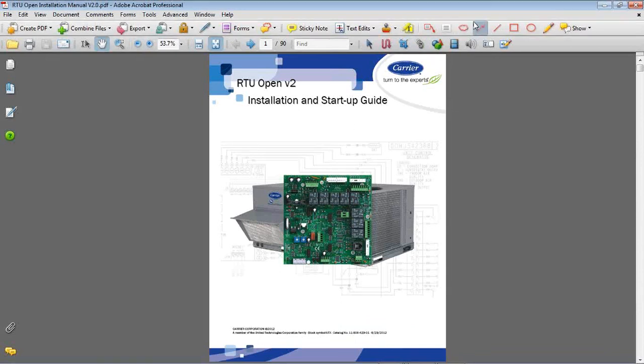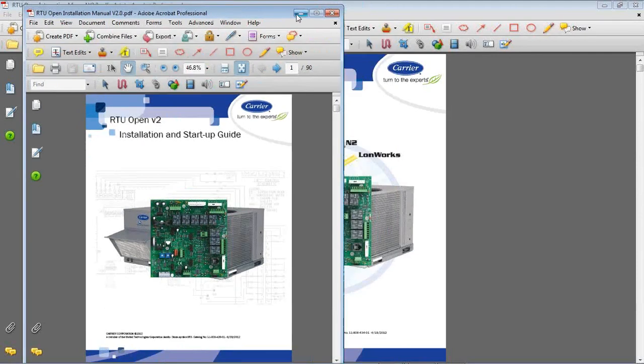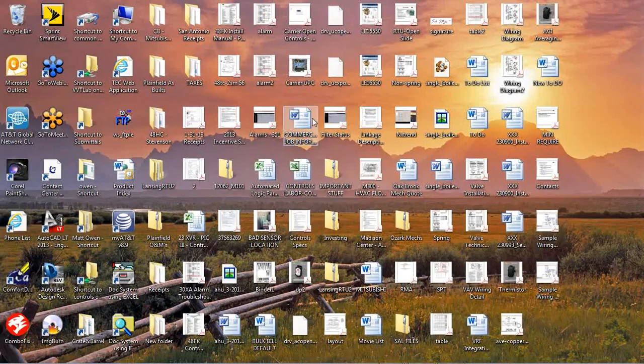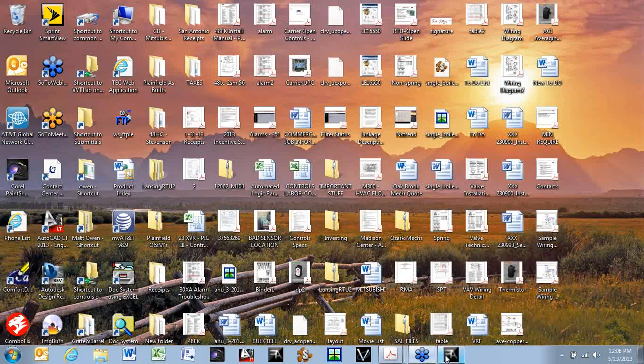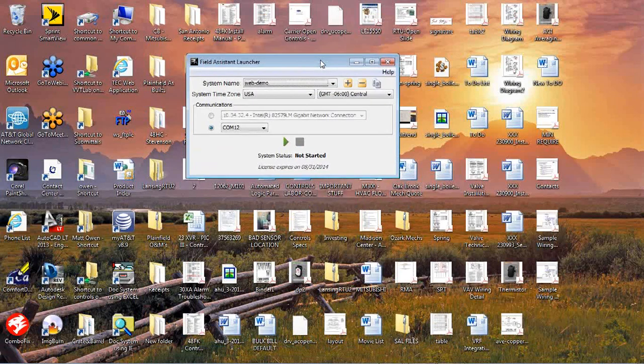So with that, we will go through the software. The Carrier software for commissioning these controllers is called Field Assistant. Okay, this is something that we can sell to you. It comes with the software, and it also comes with a USB cable that connects to your computer and can plug into any Carrier Open controller. What this software allows you to do is communicate with the controller that you're plugged into, but also communicate with any other Carrier controller that is wired into the network, the communication bus for that system.